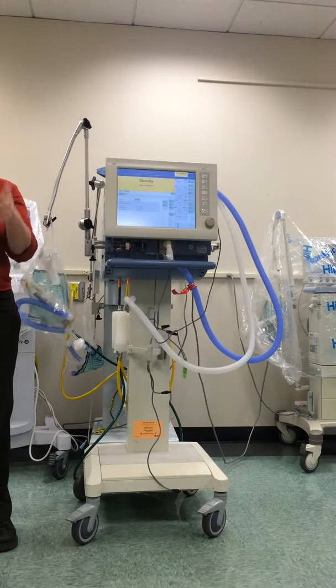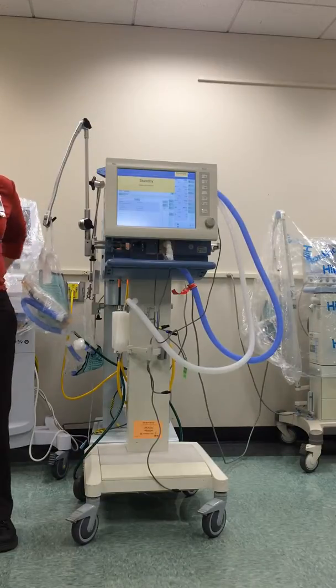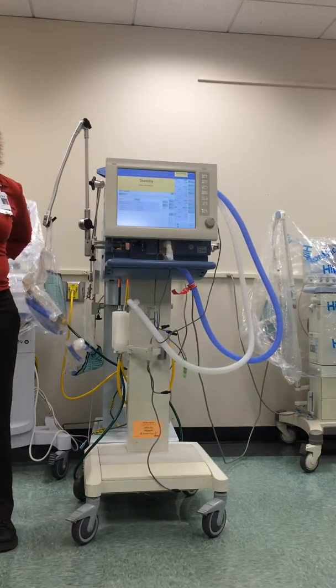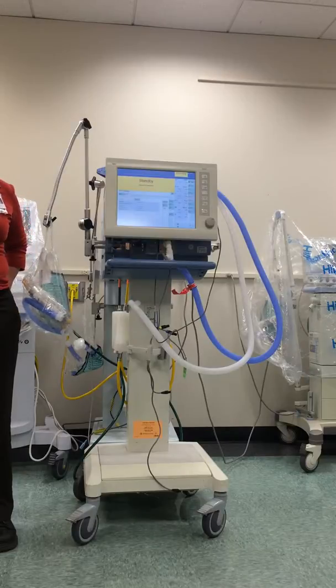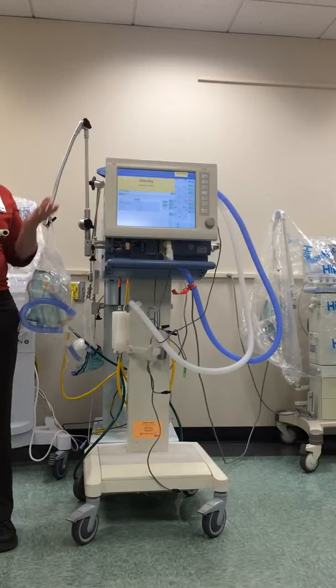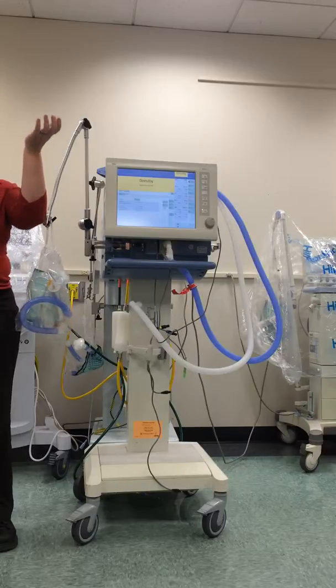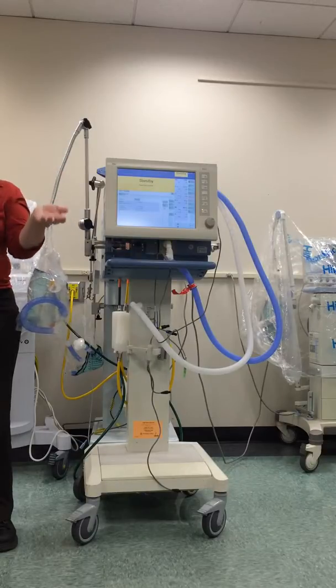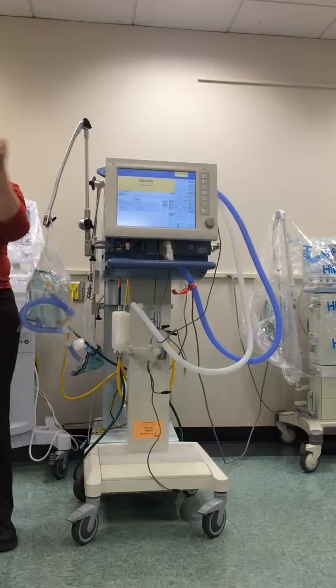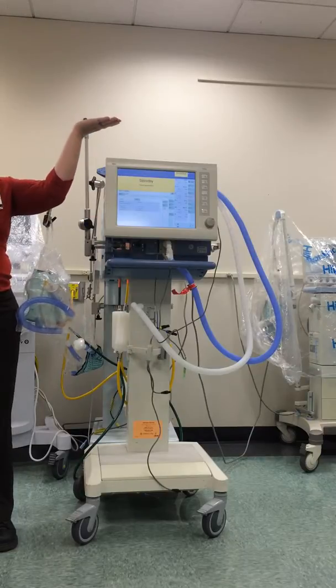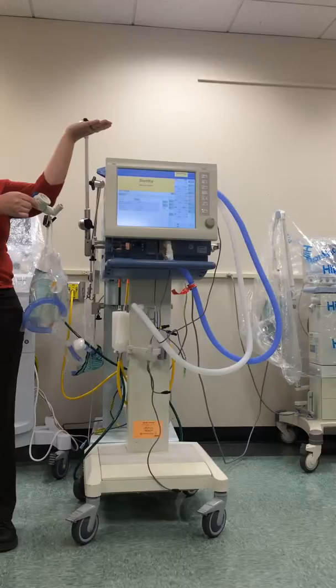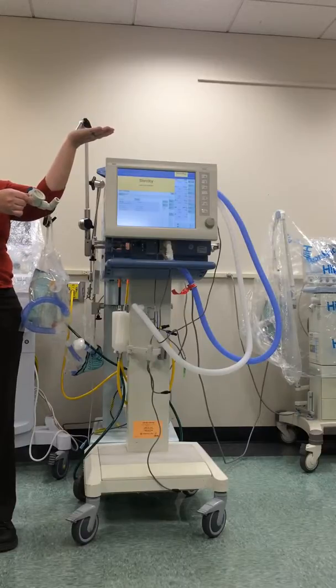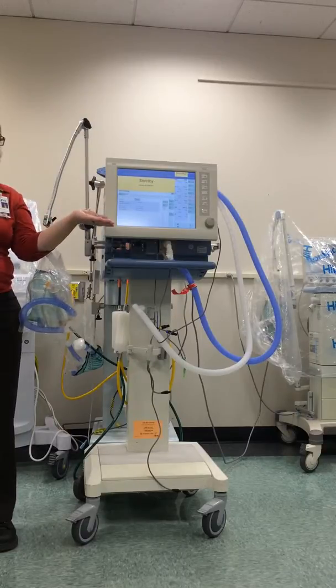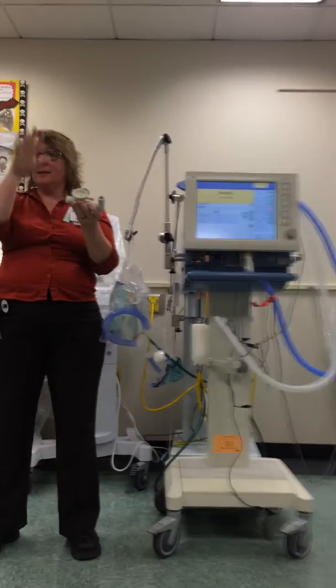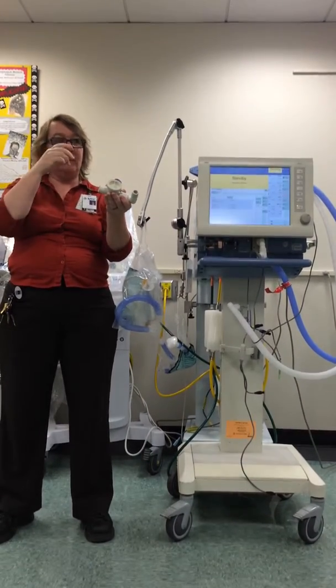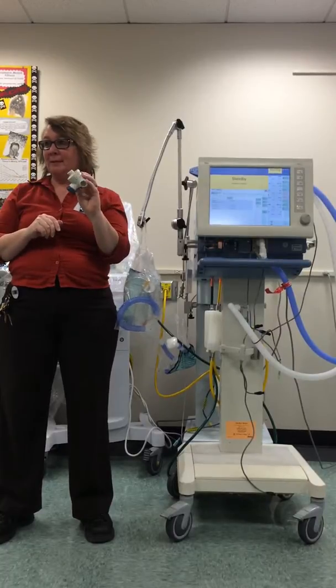So this ventilator has an external exhalation valve. I'm going to tell you more about what they are next week, but to sum it up, the vent doesn't work if this doesn't work. An exhalation valve is a valve that opens and closes. It allows air to flow out or in. So when my ventilator is giving a breath to my patient, it closes so the breath doesn't go right back in the vent. So it closes off exhalation. When my patient is ready to exhale, it opens so the breath can be exhaled back in. So if this doesn't open and close right, your patient can't get a breath. So it's a critical piece to the ventilator.